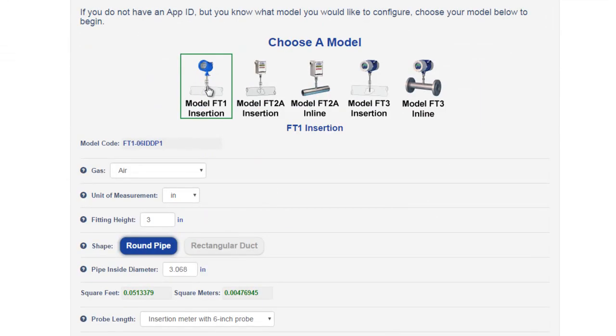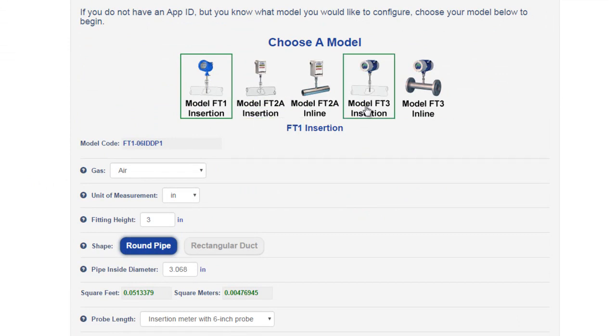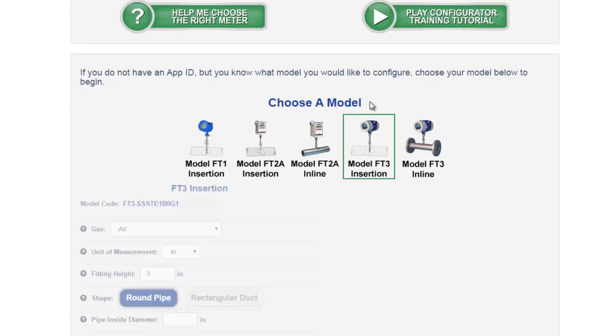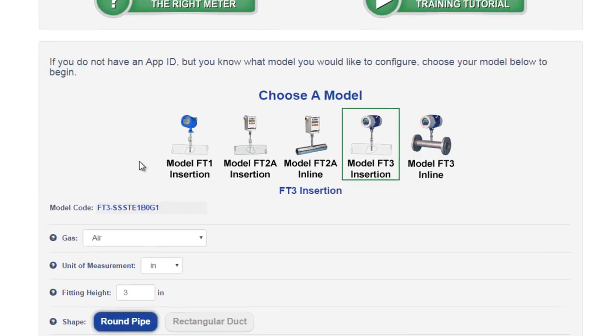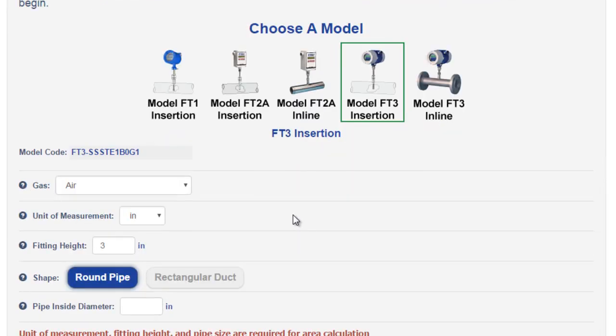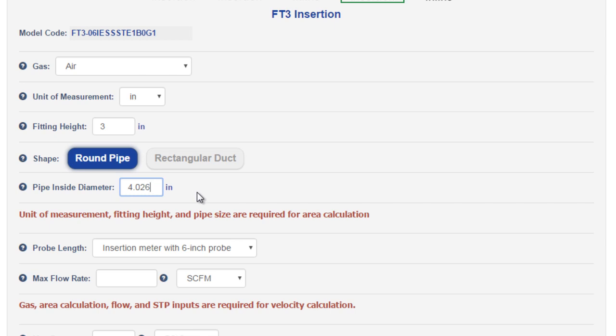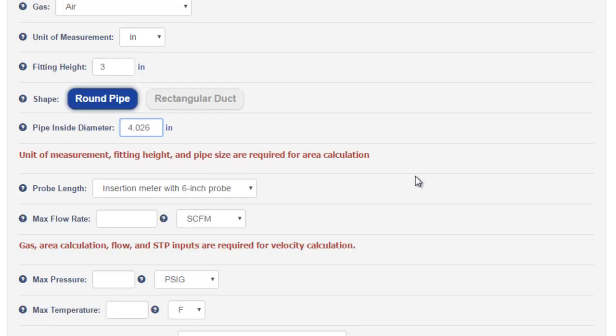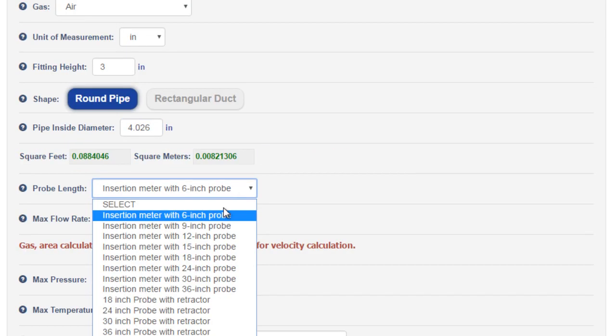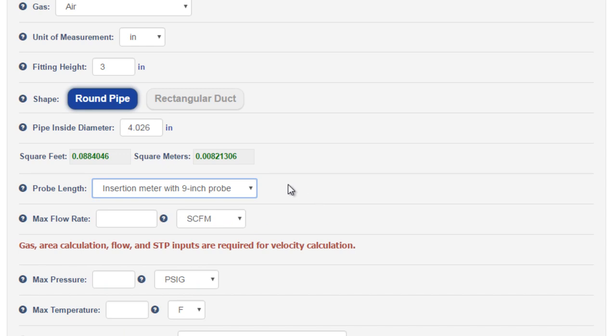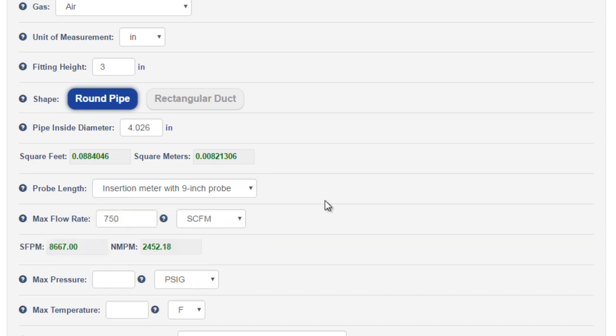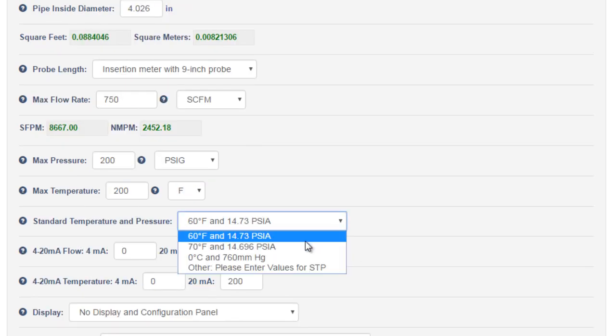Like the FT1 insertion, we also offer an insertion model, FT2A and FT3. Using the configurator for these models is very similar. Let's look at an FT3 insertion. You still need to choose a gas, units of measurement, fitting height, shape of your pipe, round or rectangular, the inside pipe diameter. This time we'll use 4.026 inches for a 4-inch Schedule 40 pipe, probe length, and we'll choose a larger probe length just for fun, maximum flow rate, max pressure, max temp, STP values, and then we get to the new stuff for the FT3.